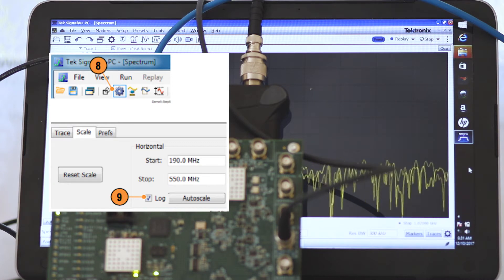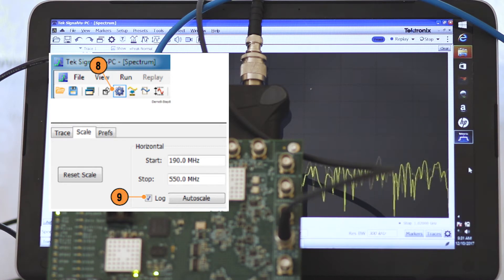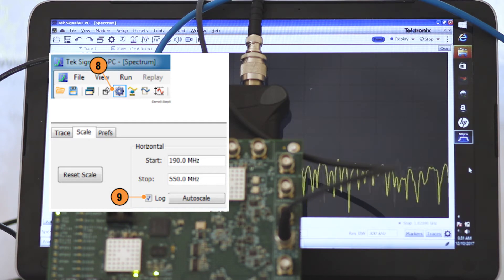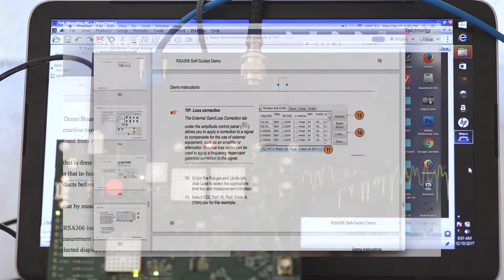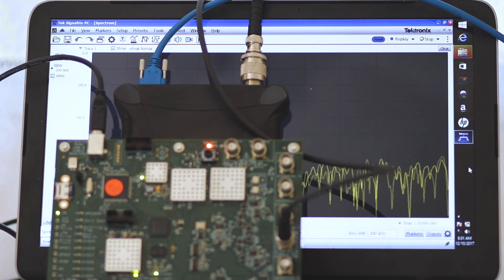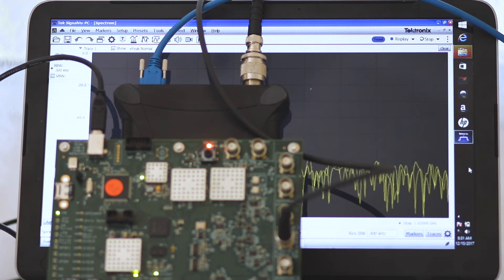In the Scales tab, select the Log Scale to reset the display to show the frequency axis in a logarithmic scale. Under the Ranges and Limits tab, click Load to select the appropriate limit line and measurement condition. Select FCC Part 15 RAD Class A 10m CSV for this example. A larger resized window of range and limit can be displayed by clicking Expand.